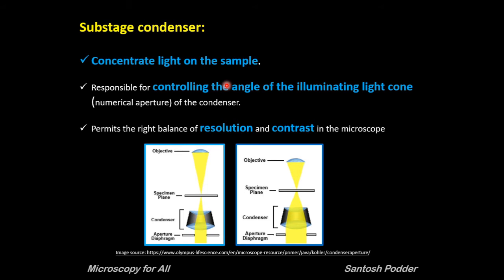The function of the condenser is to concentrate the light on the sample. The condenser is responsible for controlling the angle of the illuminating light cone, hence the numerical aperture of the condenser. Basically, the condenser controls the angle of illumination, which permits the right balance of resolution and contrast in the microscope. As you open the aperture diaphragm, you can see the cone of light illuminating your sample increasing. Correct adjustment of the sub-stage condenser is probably the most critical aspect of achieving proper light illumination. Unfortunately, condenser misalignment and improperly adjusted condenser aperture diaphragm are the main sources of image degradation and poor image quality.